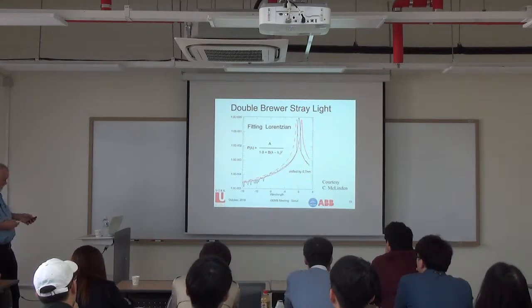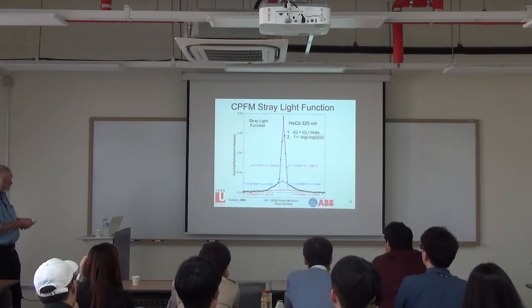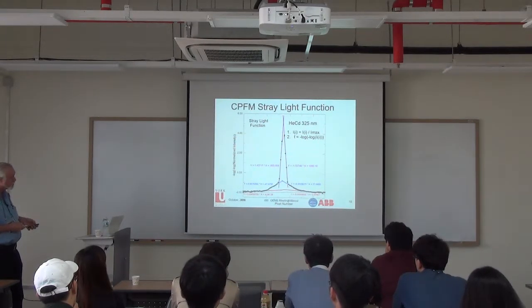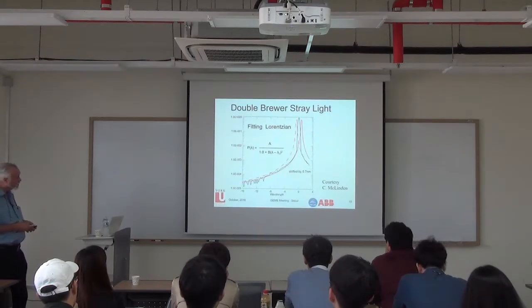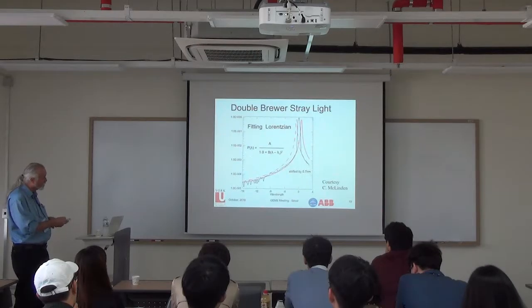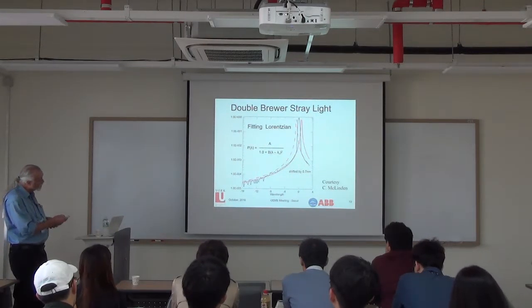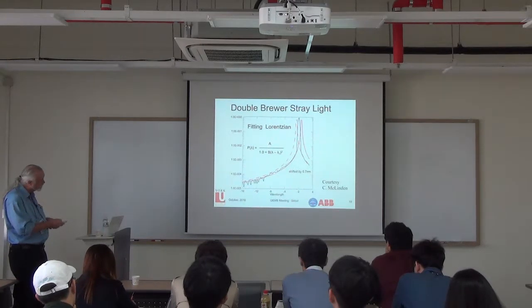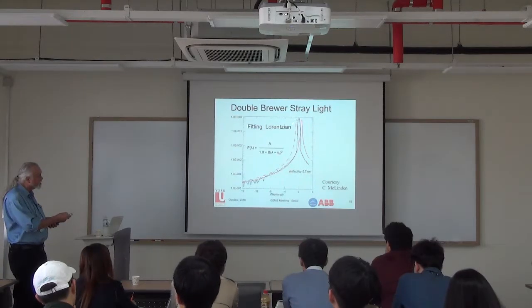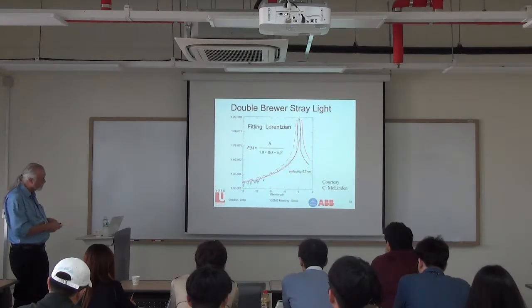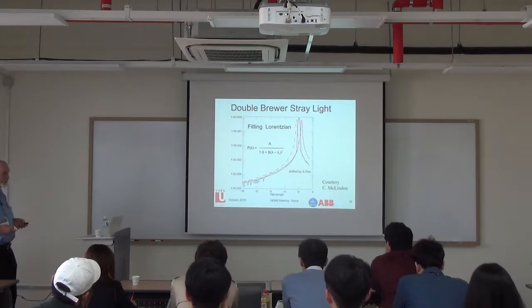What I discovered in the long run is that the wings are not necessarily straight lines—they can be represented well by a Lorentzian. In the case of the Brewer, making careful measurements as a function of wavelength, you can get a very good fit. There's the Lorentzian equation, and you can write a retrieval program to retrieve the parameters A and B. Starting with a first guess, running the retrieval, and fitting a curve that matches it—using the measured slit function out to a certain point, then the fitted Lorentzian wings to represent stray light behavior beyond that.